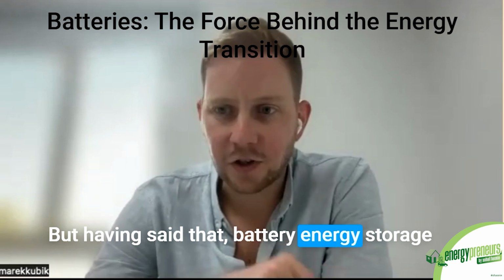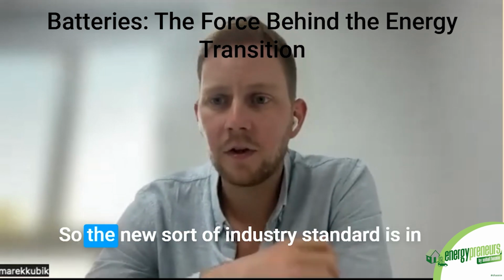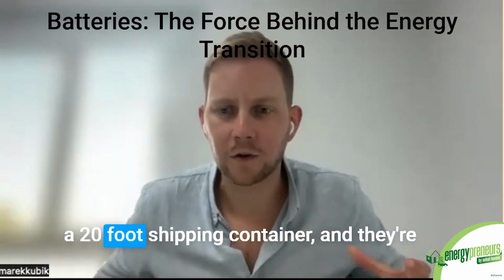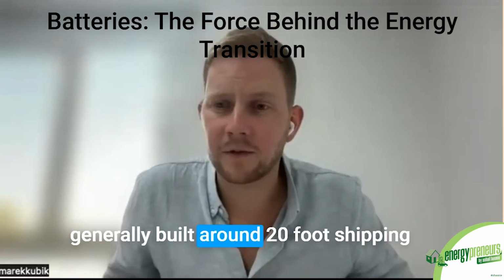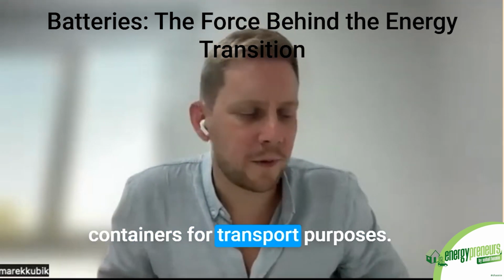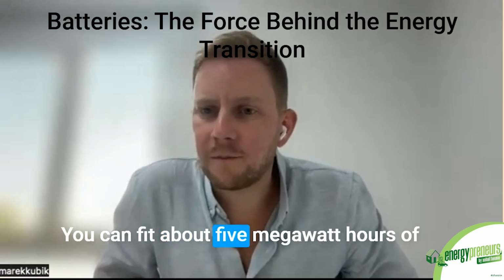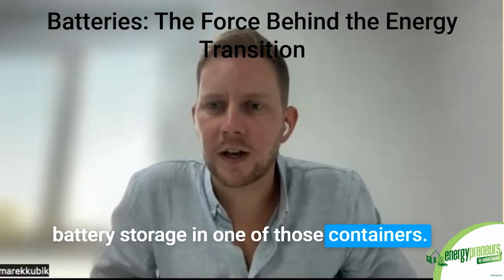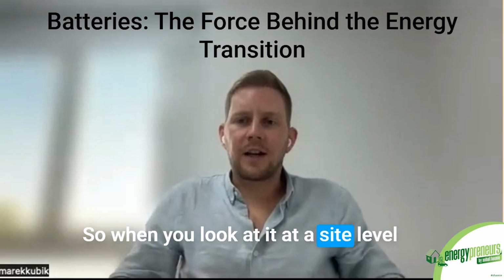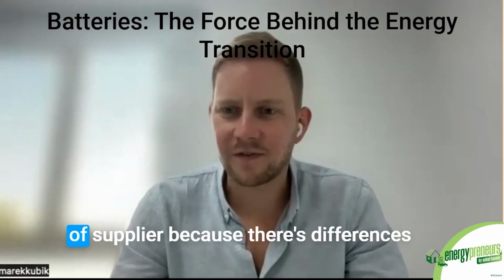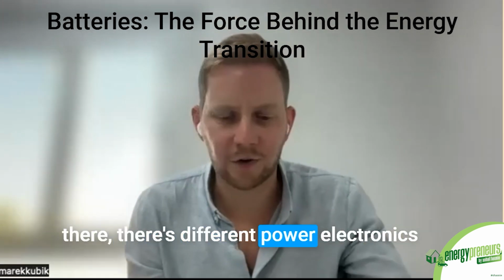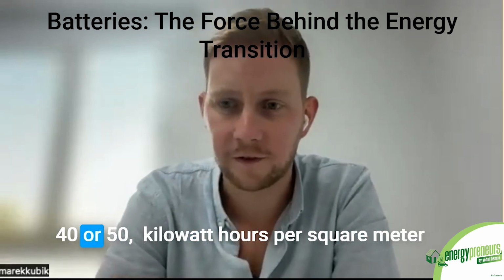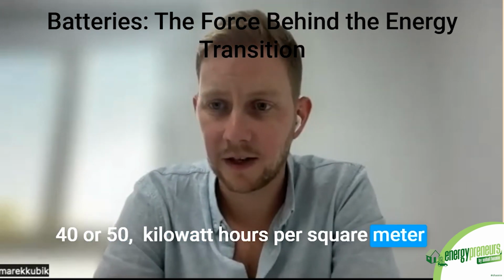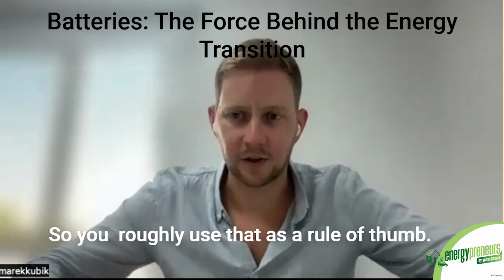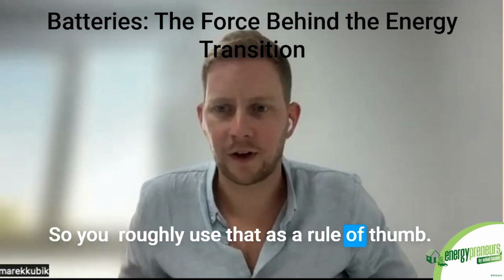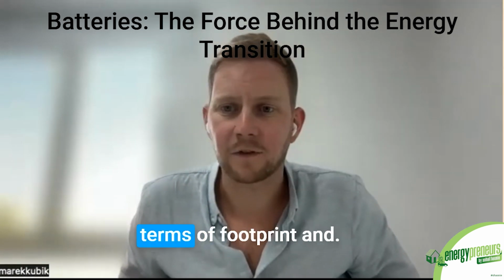But having said that, battery energy storage systems are getting denser and denser. The new industry standard is a 20-foot shipping container - they're generally built around 20-foot containers for transport purposes. You can fit about 5 megawatt hours of battery storage in one of those containers. At a site level, it depends on your choice of supplier, because there are differences in power electronics equipment, but maybe somewhere around 40 or 50 kilowatt hours per square meter is what you can get to on average for a site. So you roughly use that as a rule of thumb - it's pretty compact in terms of footprint.